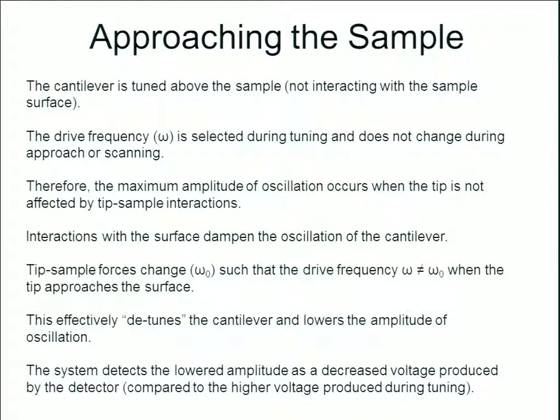As you approach and start making intermittent contact with the sample, the interaction will dampen the oscillation of the cantilever. This might change the amplitude or the phase. If there is a phase lag or amplitude shift, this is basically detuning the cantilever. The piezoelectric will make the appropriate changes, and we record that data to eventually plot it in a 3D representation.